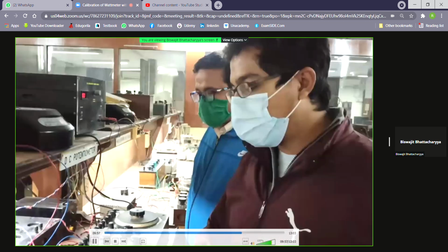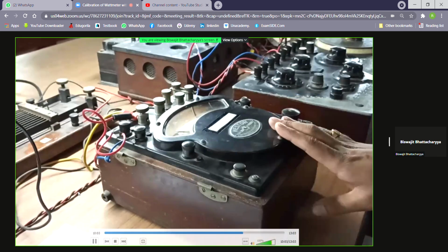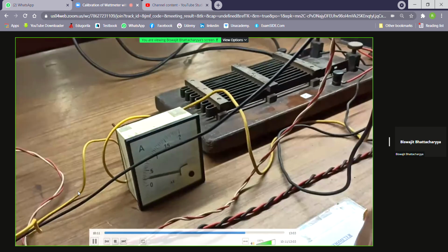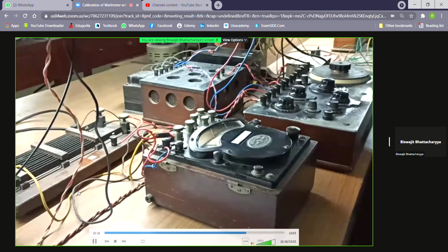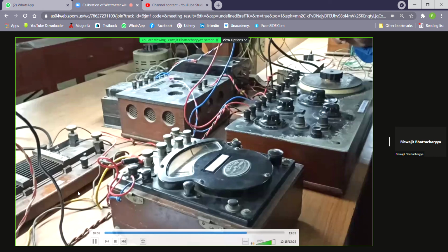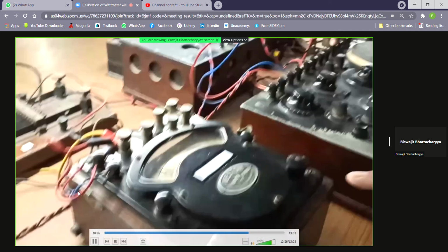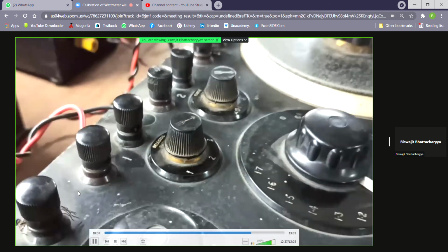Now we have checked the output voltage V1 for 20 watt, with link and without link condition. We need to take the value of the wattmeter also for these two. Now we calculate the current. That means we will check the voltage V2 and the resistance R, which is connected in terminal 3. So we will change the selector switch to 3 and the range as well to 0.1.